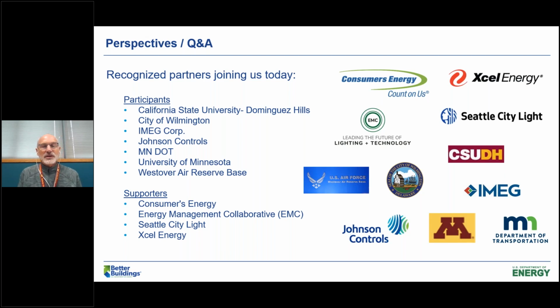Felipe, you're asking us to share what was most meaningful, and I think for this particular project, going to a standby temperature was key. That means if our temperature is 72 degrees in a space, when there's no one in that space, we allow that temperature to drift up or down 2 or 3 degrees, depending on winter and summer. We call that standby mode, which is different from unoccupied, which drifts a lot further, 8 to 10 degrees at night. But the standby was the real feature that we found meaningful.